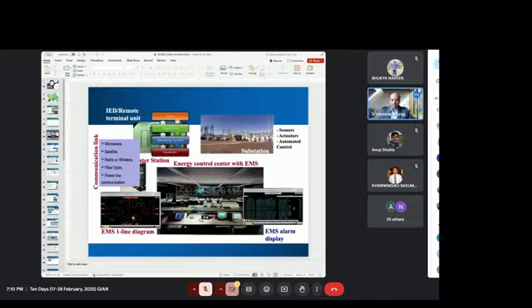Now if you look at the whole infrastructure, you have a substation, which is physical, and that is where we put more and more IEDs. Sensors exist throughout the feeder too, but the substation is the first major data collection point. Things are changing now, and we are putting some kind of data collection point at the pole also, but those are rare. The substation is the place where the voltage changes, high to low, low to high.